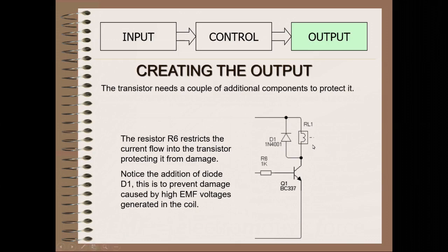To explain it real quick, let's say we have the relay coil energized. It has a magnetic field around it when it's energized. Whenever you de-energize a coil, that magnetic field collapses. As it collapses, it will actually induce a voltage into its own self across its own set of coils, and it becomes a power source. And if you didn't have a place to allow that voltage to return back to itself, because it is momentarily, in a fleeting moment, a power source, then it would otherwise go through the electronics and damage them.